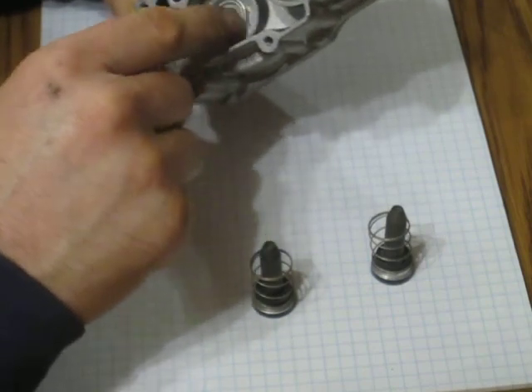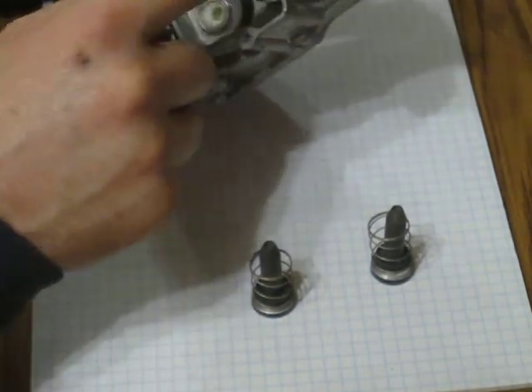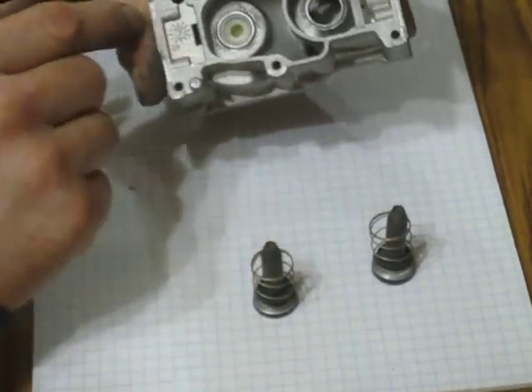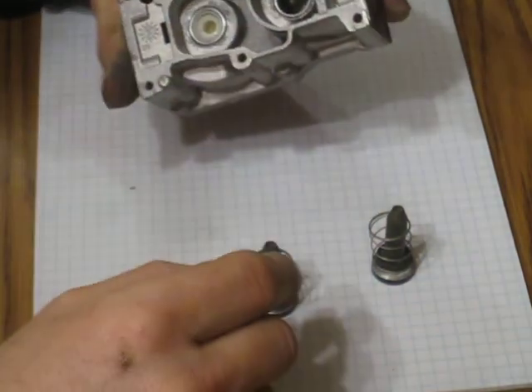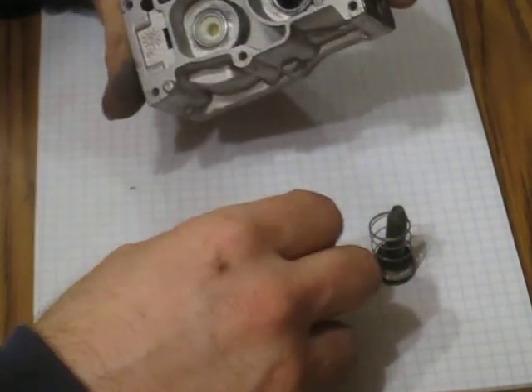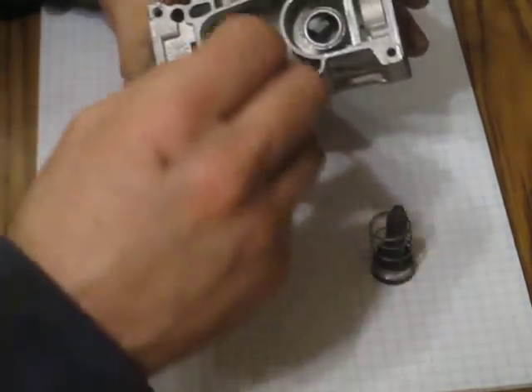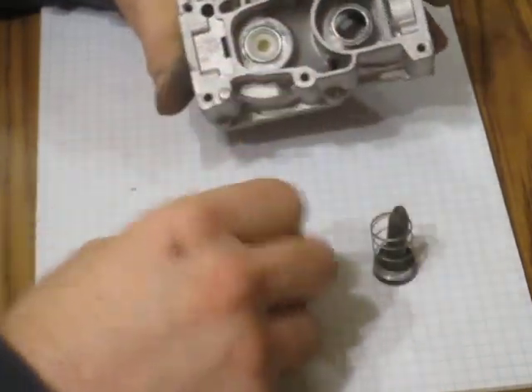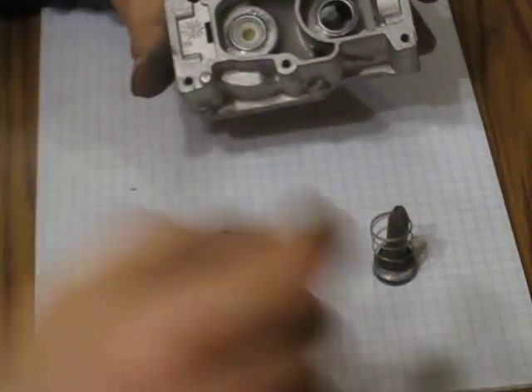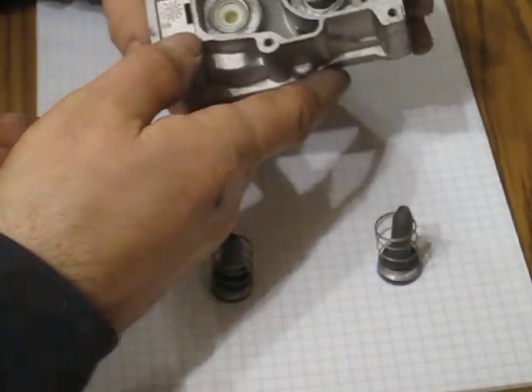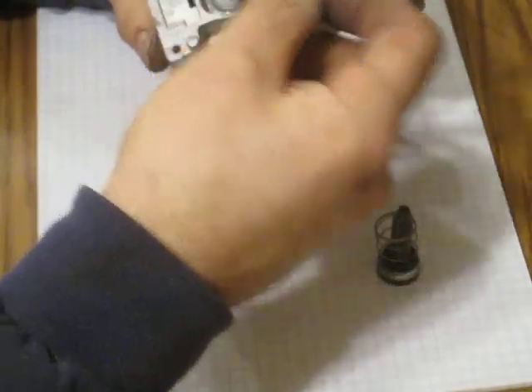I also took some 600 grit paper and went over the seats for the valves to make sure that they're clean. They had a little crap on them as well, so now these should seal up nicely. Reassembly is the reverse of disassembly. I'd say put this gasket on first, the big hole and the small hole.